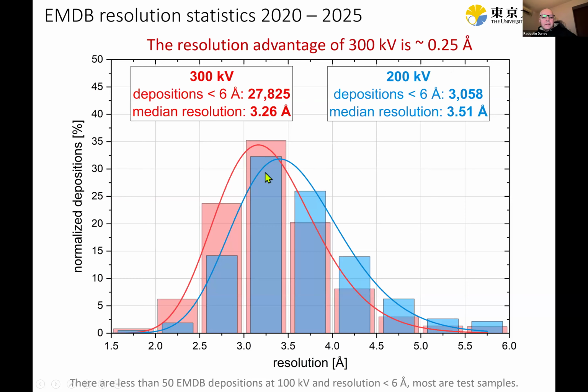So the devil here is also in the detail, and if you look at the high resolution region below 3 angstrom, then we see that the discrepancy is getting bigger. For example, in the region between 2.5 and 3 angstrom, the 300 kV is about 2 times more prolific, relatively speaking, because these are normalized histograms. And in the region below 2.5 angstrom, it's 3 times more prolific than the 200 kV. In these regions is where we get good quality maps that help us get higher fidelity models, better modeling of side chains, also small molecules, if we have some kind of a ligand, and water molecules, which are becoming more important for evaluating and investigating the function of proteins.